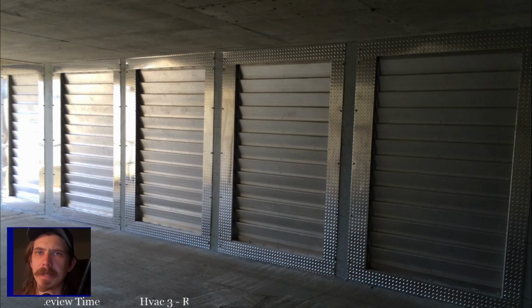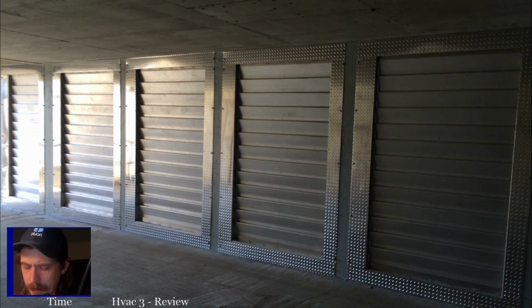It basically takes that signal, turns it into DC, chops it up, makes it look like an AC waveform, and sends it out to the motor. Okay. And that is way more reliable than analog SCR rectifier VFD units. All right. And the biggest deal with that, the other good benefit that you're going to see out of that, and I'm trying to find the exact spot where it says it, but I just want you to remember that you will have reduced problems with harmonics when it comes out of those two.